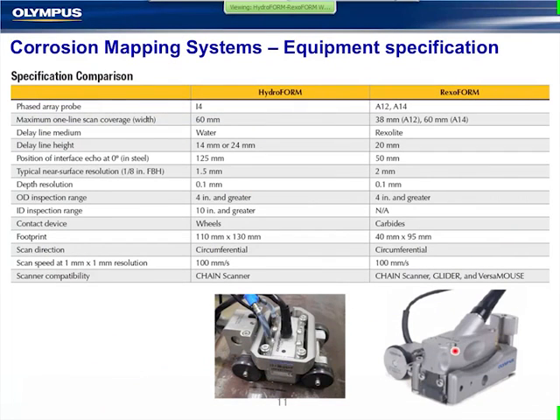So, the two specifications for these, and you'll find this in the brochure as well: the HydroFORM using the I4 probe, the RexoFORM using either the A12 or A14. These are very common weld inspection probes, and if you already own those probes, they can be used and are compatible with the mechanics that you see here of what we call the RexoFORM. This I4 probe is typically for an immersion tank, so most of the attendees unlikely would have that unless they're using a HydroFORM already.